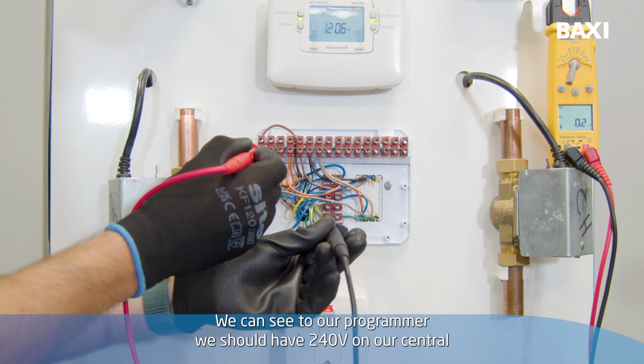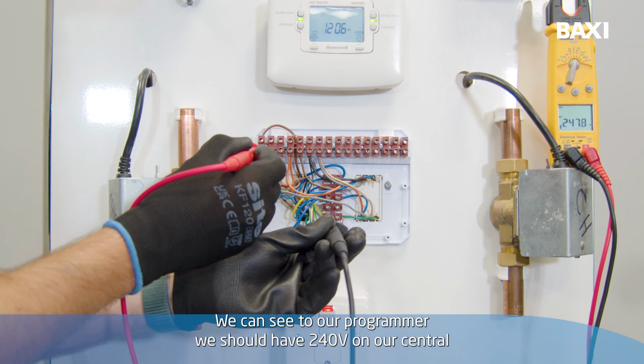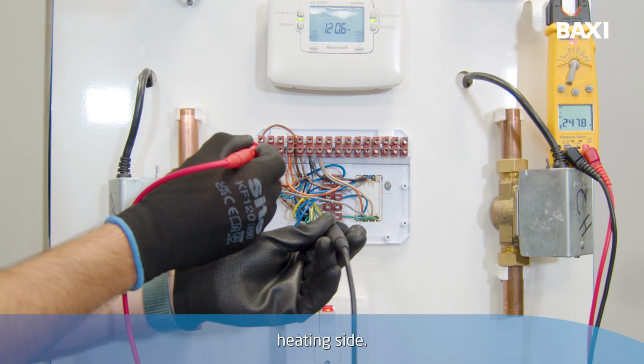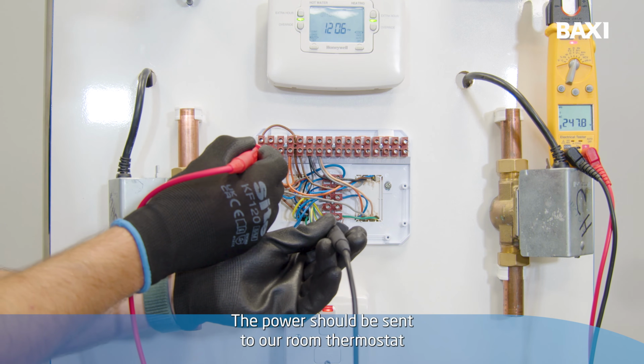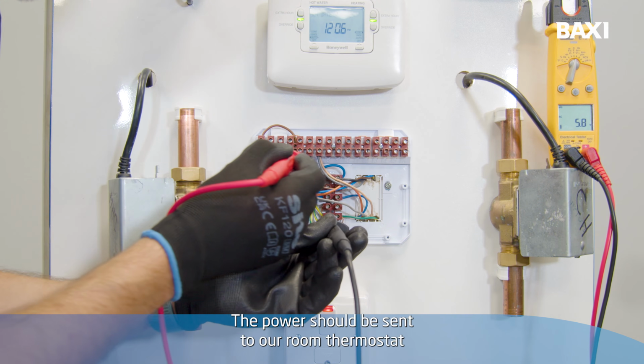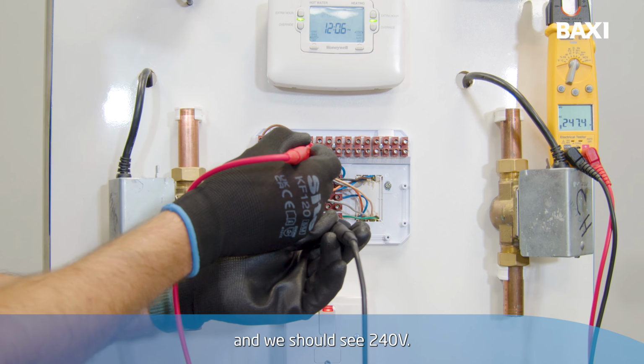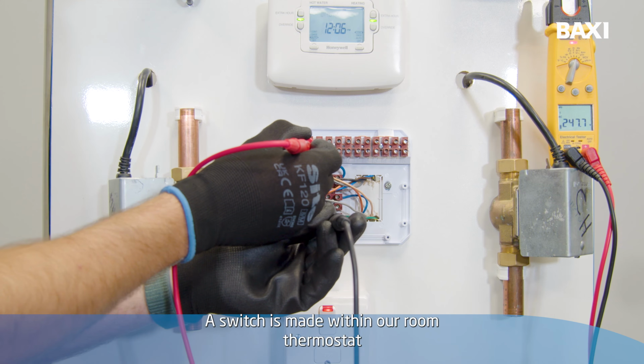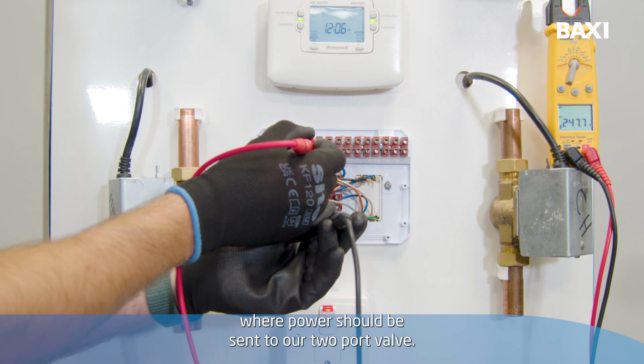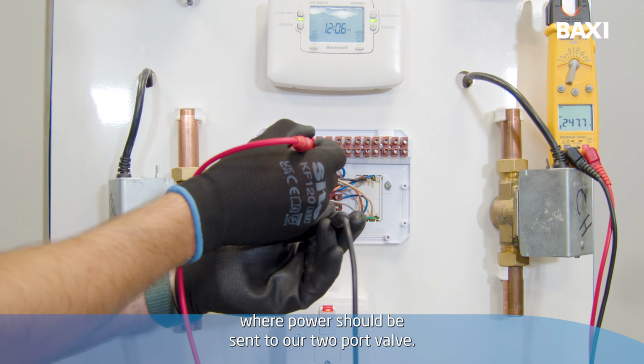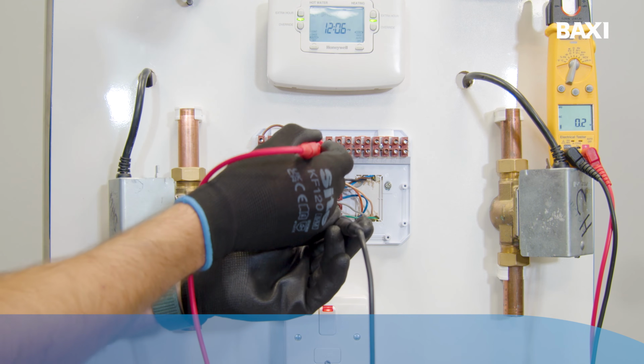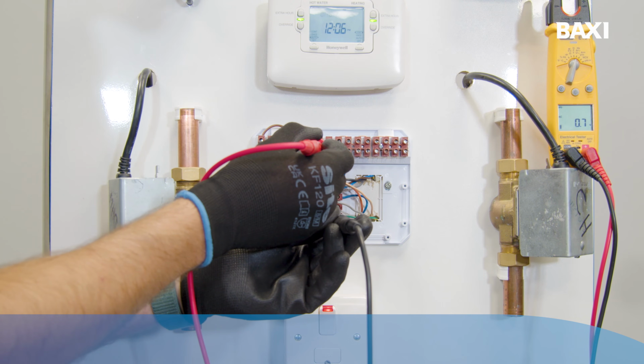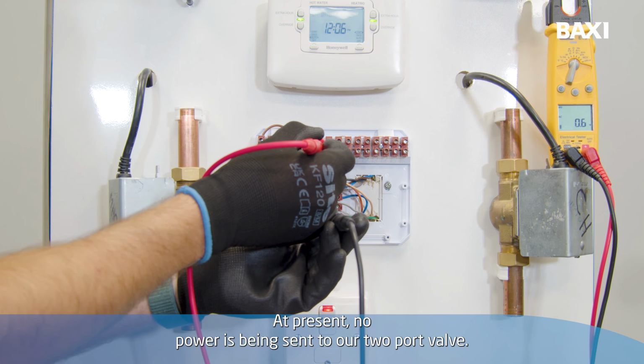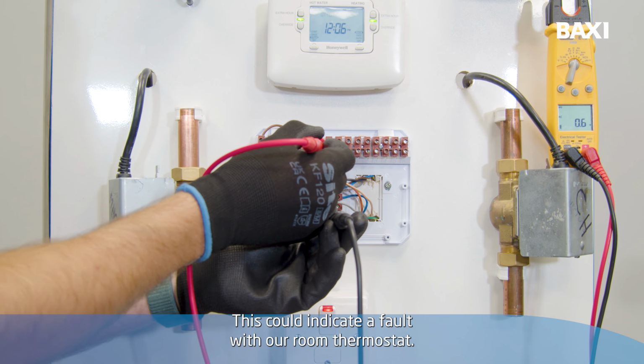We can see to our programmer, we should have 240 volts on our central heating side. The power should be sent to our room thermostat and we should see 240 volts. A switch is made within our room thermostat where power should be sent to our 2-port valve. At present, no power is being sent to our 2-port valve. This could indicate a fault with our room thermostat.